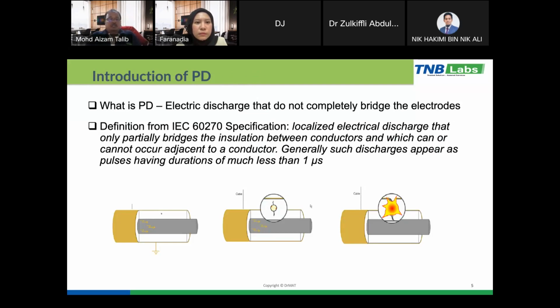So, introduction of the PD. What is the PD or partial discharge? It is an electrical discharge that does not completely breach the electrode. Electrode means a conductor to a conductor, or a conductor to the ground. If this fault or discharge completely breaches the electrode, then we call the phenomenon a full discharge or arcing. So partial discharge means that it is not completely breached.